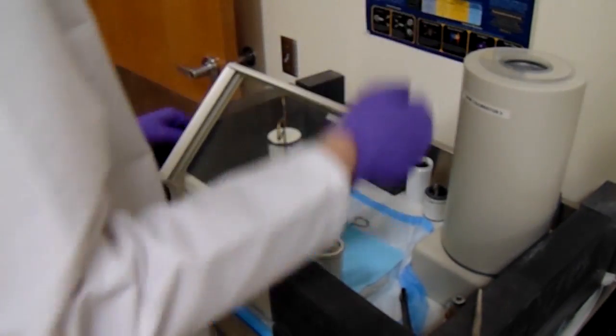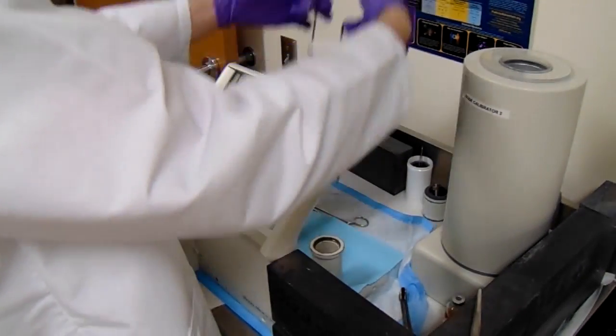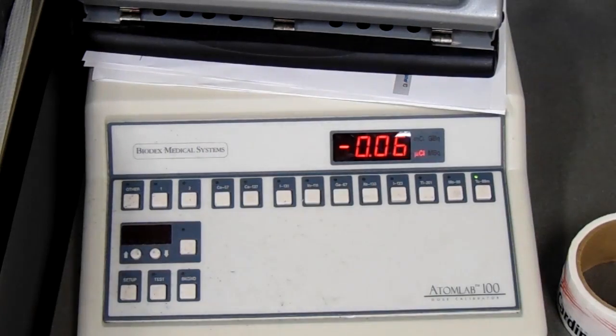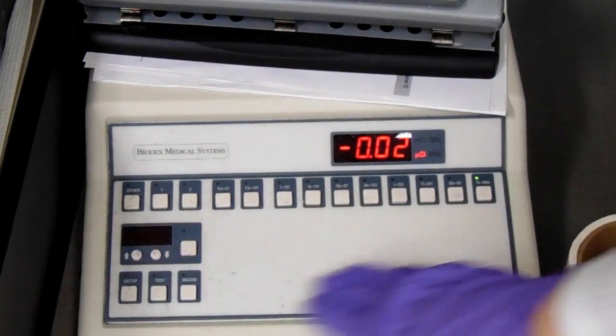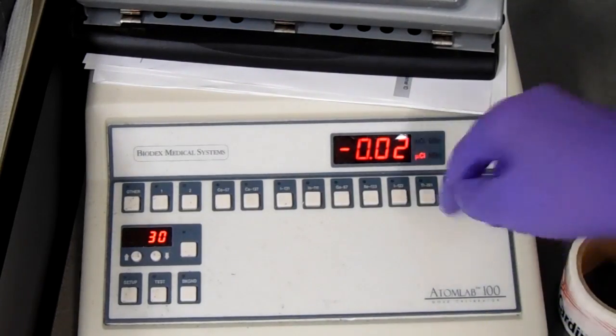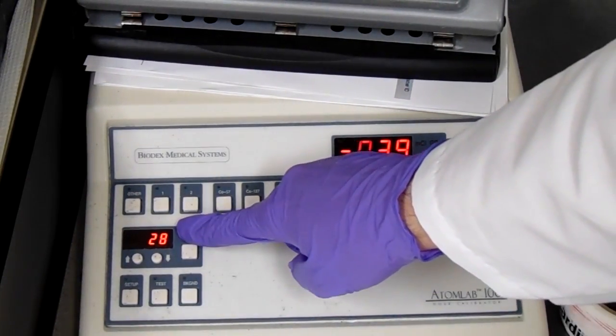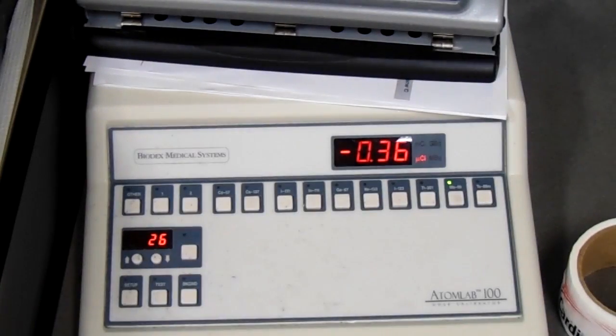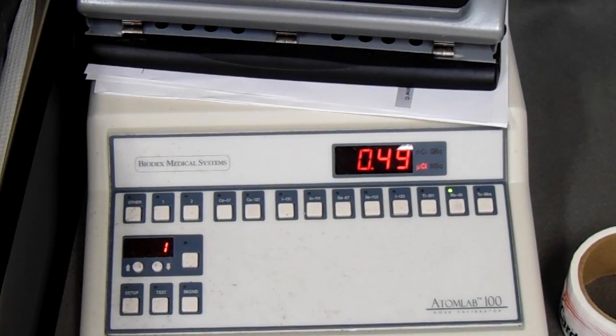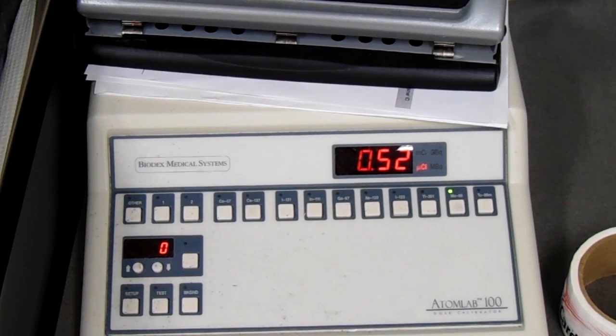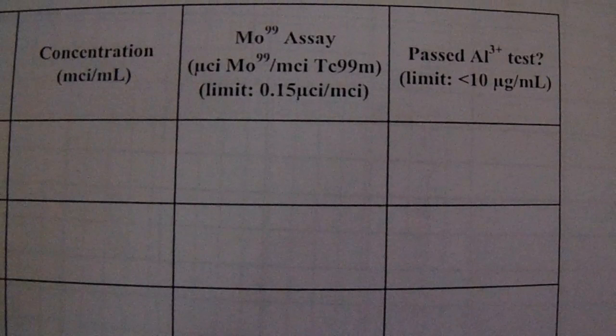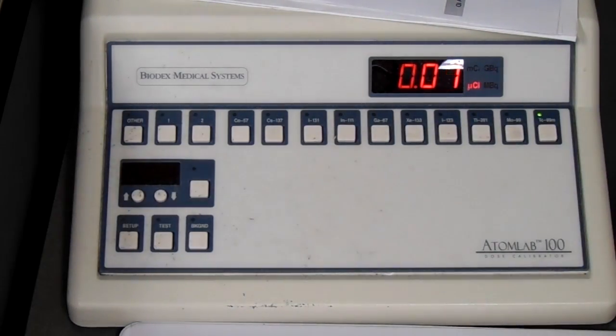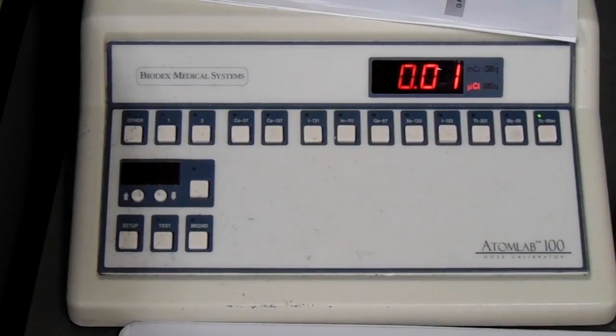Next, we're going to take the plastic sleeve out of the calibrator and slide our moly pig into the calibrator. And then we're going to come over and hit molybdenum, and it's going to count down for 30 seconds. At the end of the countdown is when we'll get our reading. Once the countdown is finished, we take our reading and record it in our moly assay box. We'll get back to that later. And then hit technetium when we're done.